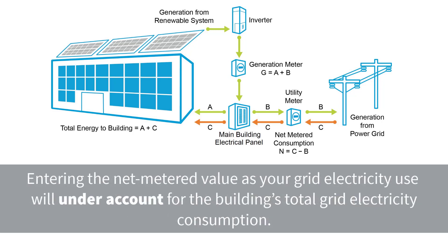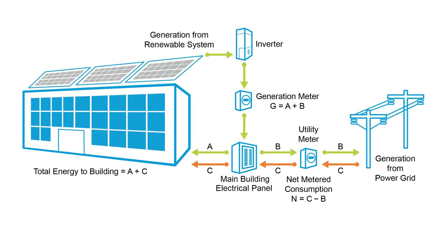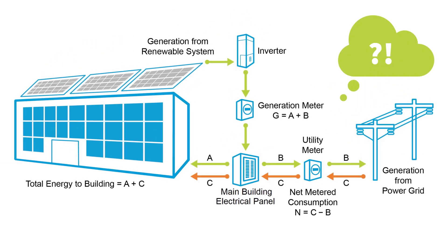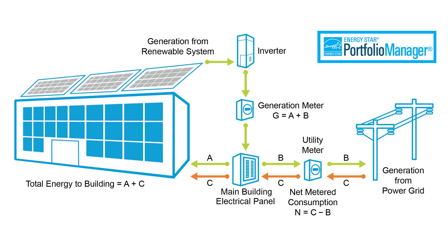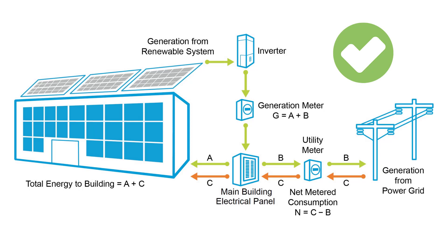Entering the net metered value as your grid electricity use will under-account for the building's total grid electricity consumption. The answer is that Portfolio Manager differentiates between the energy you consume from the grid and the energy you consume from on-site generation. Essentially, your energy metrics are getting a credit for on-site renewable electricity consumption compared to grid electricity consumption, so it's important to be able to differentiate the two.